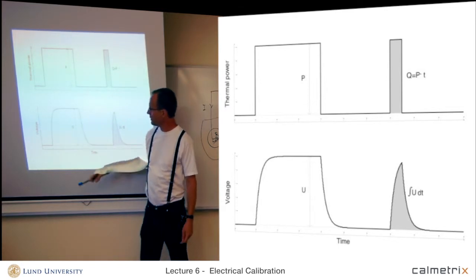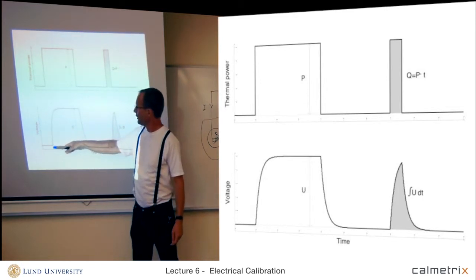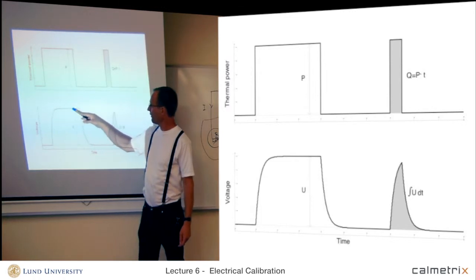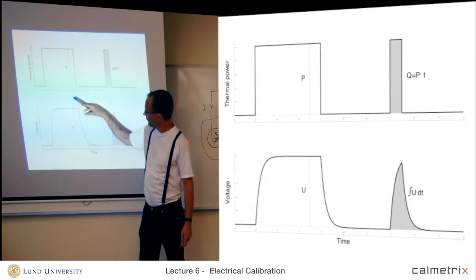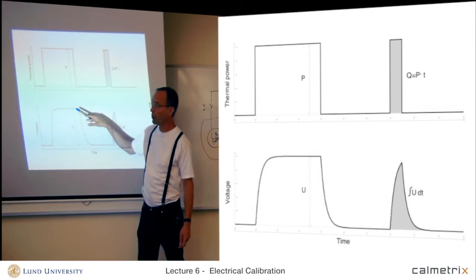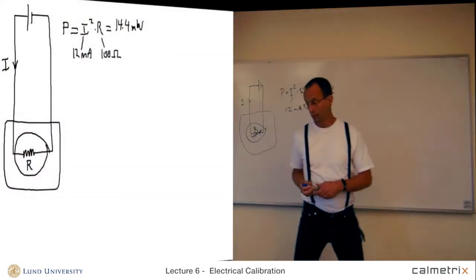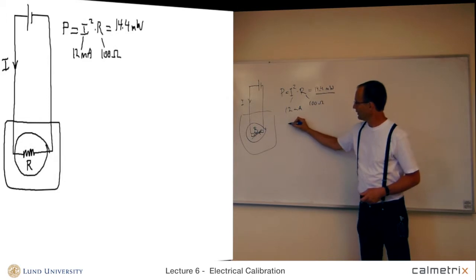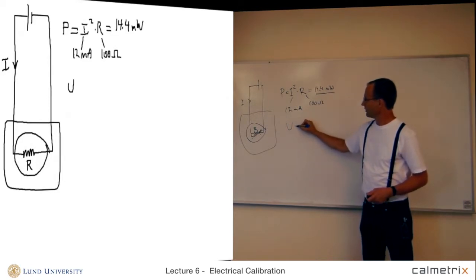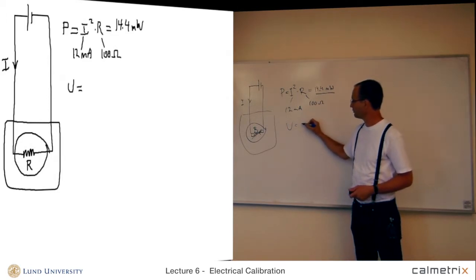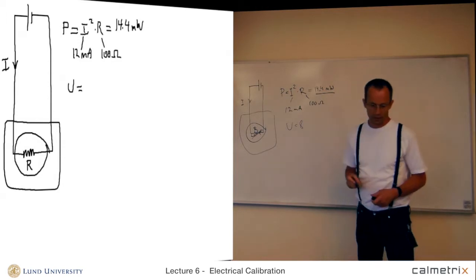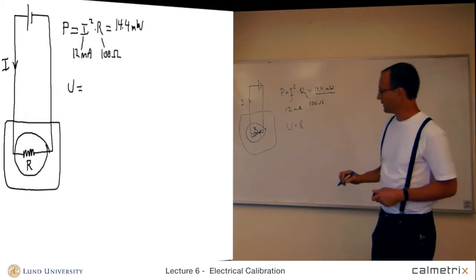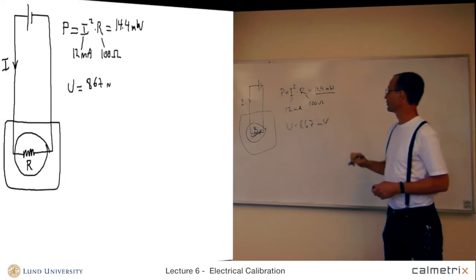And the output from the calorimeter looks something like this. Go up to a steady level and then go down again. And if you look at the steady state part, we have a certain voltage output from the heat flow sensor. This is called U. Let's assume that this is 867 millivolts.